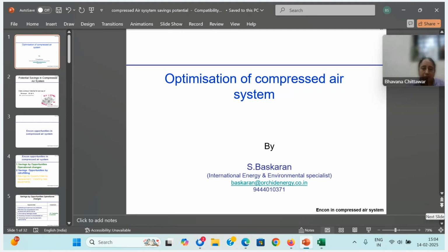I achieved close to 50 to 60% in some leading industries by various measures in compressor systems alone. We cannot achieve that much savings in any other utility, either pumping or steam or electrical. Achieving 10 to 15% is a very good achievement. But in compressor systems, there is always potential to achieve more than 50%. We can reduce the number of compressors operating and throw away some compressors. It is possible.